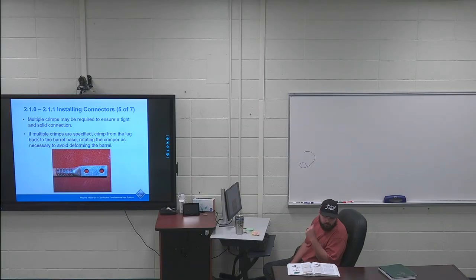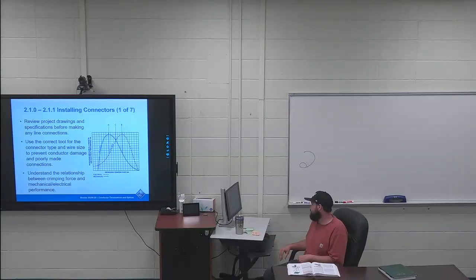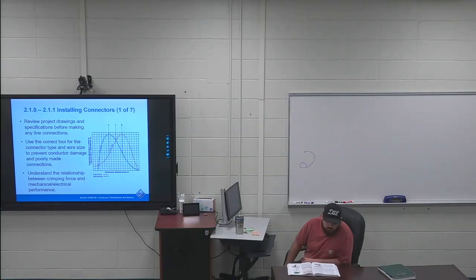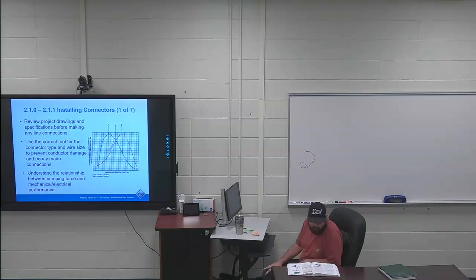Page 14, installing connectors, 2.1.1 installing compression connectors. This graph is going to be important. Your mechanical advantage or your best mechanical spot versus your electrical spot are at different places. So you're going to want to find a middle point, which is point C on the graph. Second paragraph, second sentence to the end is highlighted. Maximum mechanical strength A occurs at a lower crimping force than the maximum electrical performance B. The point of intersection C represents the ideal crimping force. Using a crimping die that's too large results in poor electrical performance and using a die that's too small produces a weak mechanical connection.